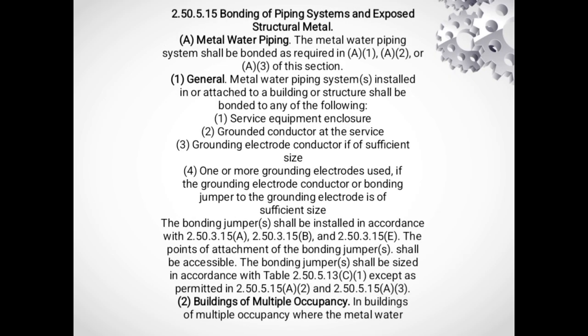2.50.5.15 Bonding of piping systems and exposed structural metal. A. Metal water piping. The metal water piping system shall be bonded as required in A1 and A2 or A3 of this section. General metal water piping system. Number 1, a general metal water piping system installed in or attached to a building or structure shall be bonded to any of the following. Number 1, service equipment enclosure. Number 2, grounded conductor at the service. Number 3, grounding electrode conductor if of sufficient size.